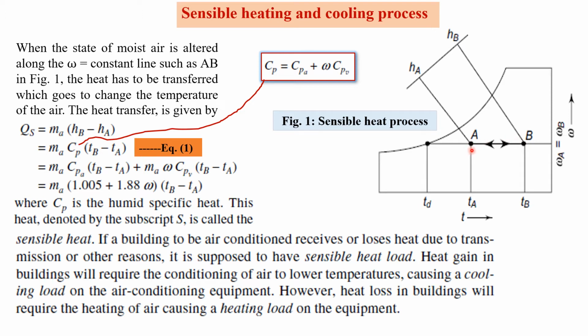There is one limit during sensible cooling. If we maintain the cooling coil at lower and lower temperatures, the air is sensibly cooled, but it can only be cooled down to its dew point temperature. If we try to maintain the cooling coil at a temperature lower than the dew point temperature, it will result in the removal of moisture. Condensation of moisture will take place, and that will bring down its moisture content, or specific humidity. So sensible heating can take the moist air to any desired temperature, whereas sensible cooling is permissible only up to the dew point temperature of the given sample of moist air.